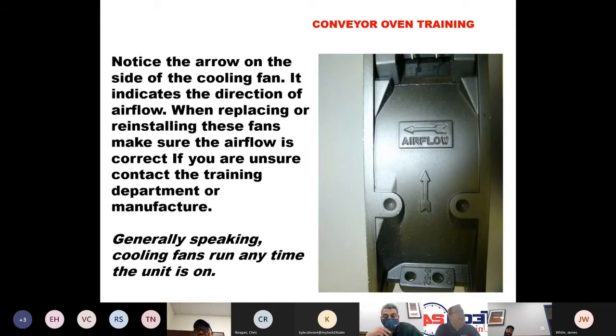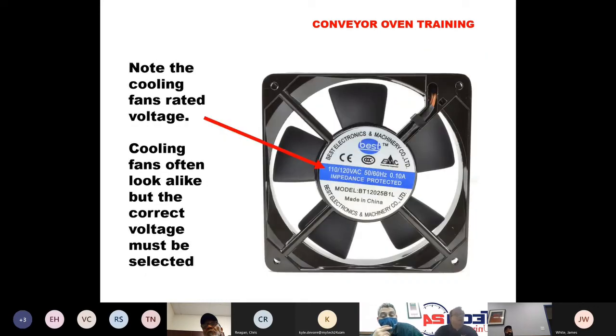On this fan, you can see that there's arrows that tell you which way the airflow is going. On conveyor ovens, we want that airflow to be going in towards the controls and the motors. Generally speaking, these fans are going to run anytime the unit is on. These fans also are rated for voltage. You must make sure that you're getting the correct voltage replacement fan when you're replacing these. The easiest way to do that is to make sure you order the OEM, but it's still a good idea to always check the voltage before you install anything to make sure it matches your supply voltage.